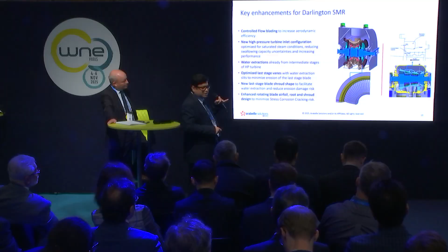Then we have the optimized 40-inch rear stage. So the last stage blade remains very much the same from our legacy machines. It has a lot of experience. What we changed are the guide vanes. Guide vanes are designed with a hollow suction blade with slits for water extraction, and this water is taken from the diaphragm to the outside. And that also improves the lifetime of the last stage blade.